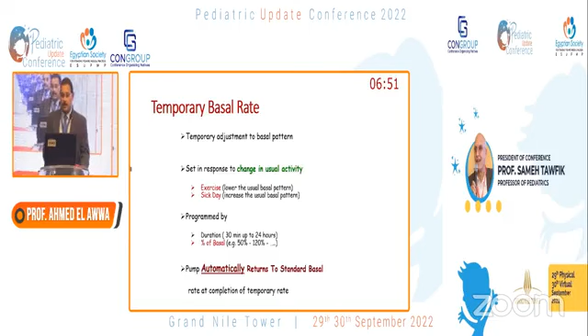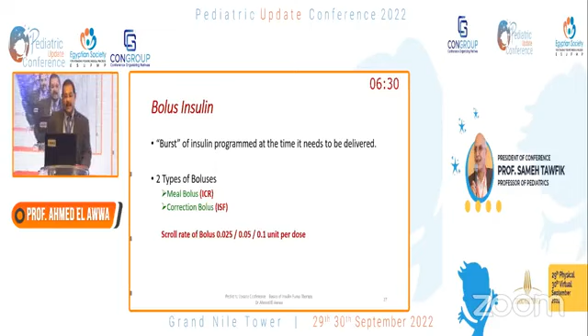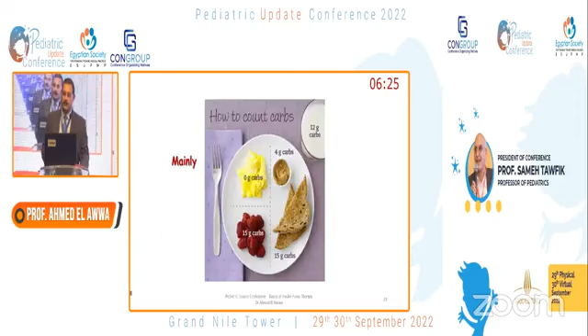For the bolus, you have to be familiar with the carb counting. You put the carb count to the pump. The pump will calculate based on what we call the insulin carbohydrate ratio, and it will correct the high blood sugar based on what has been fed to the setting as the insulin sensitivity factor or the correction factor. And it can give the bolus as precise as low as 0.025 unit.